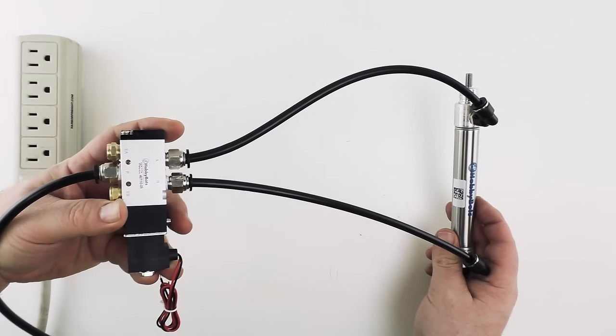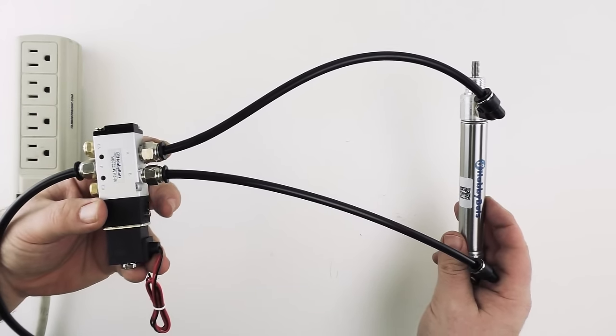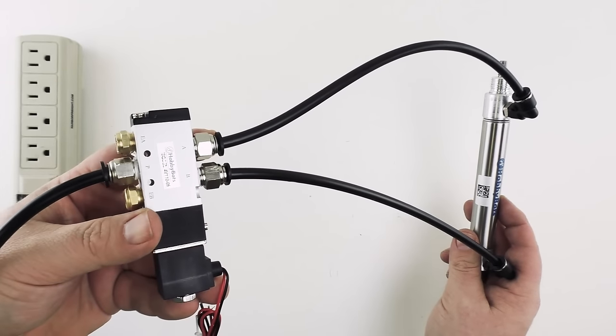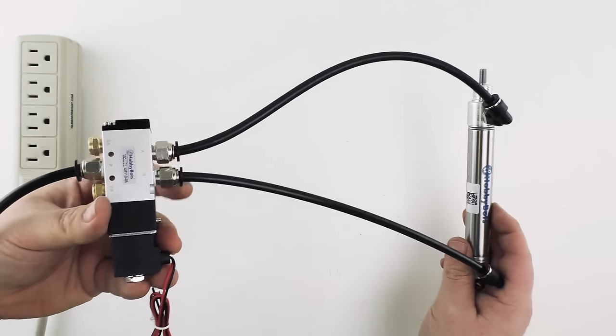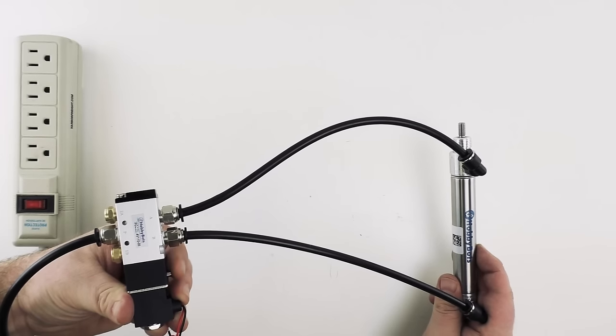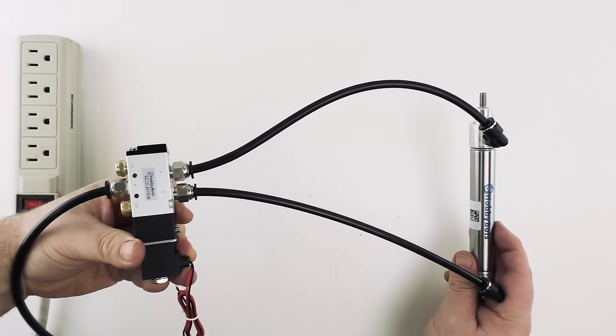We can now test our solenoid to make sure it's operating properly. You can see that there's a small silver button here on the edge of the solenoid. We can go ahead and depress that and it will actuate our cylinder. Alright that's working fine.